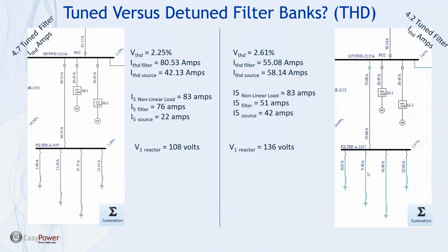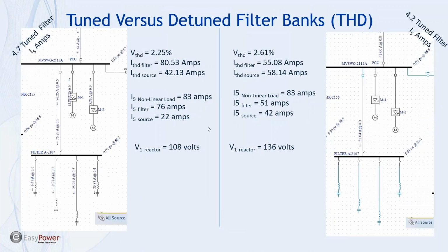So whether it's tuned or detuned, both systems are taking in harmonic currents, and the reactors are being subject to harmonic loading, and therefore it has to be analyzed through some type of analysis.